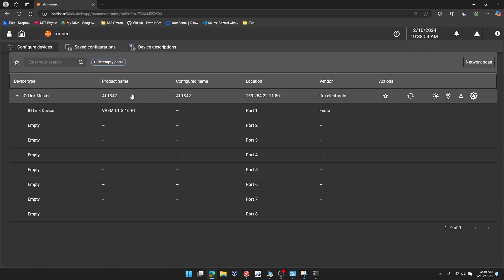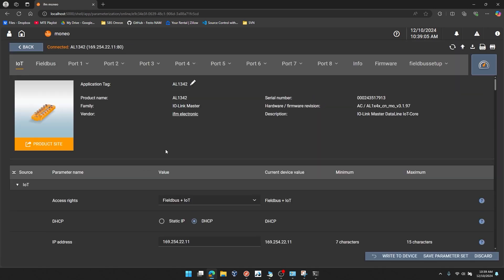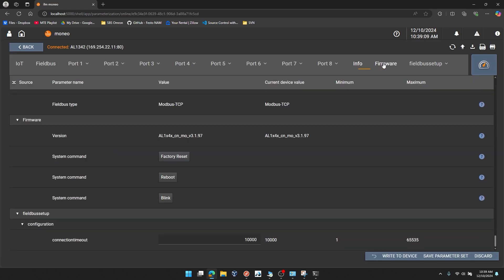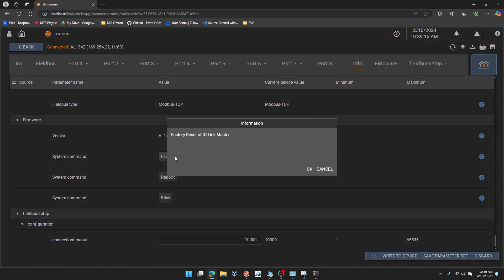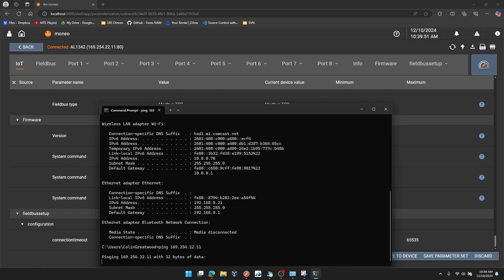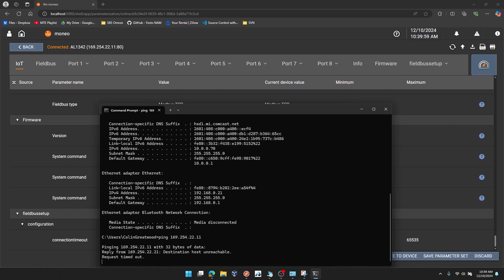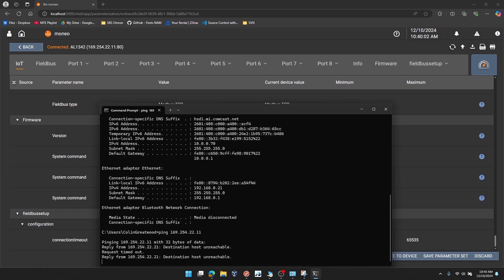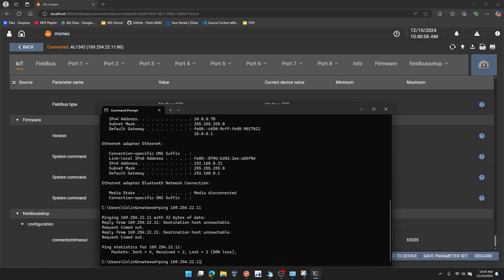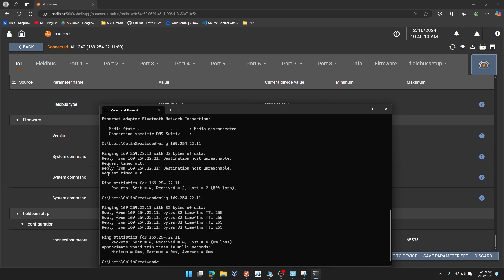So my next step, just to make sure that I'm starting at defaults, I'll click on the IO-Link master, wait for it to pull up its fields, go down to the firmware section. And you can see there is an option for system command factory reset. I'm going to click factory reset. And I'll acknowledge the pop-up. If I'd like to see when this device turns off and on, I can go and I can try and ping that IP address. You can see right now, I wasn't able to ping it. If I wait a few more seconds and I do the same ping, you can see that it's cycled power and now it's been factory reset.